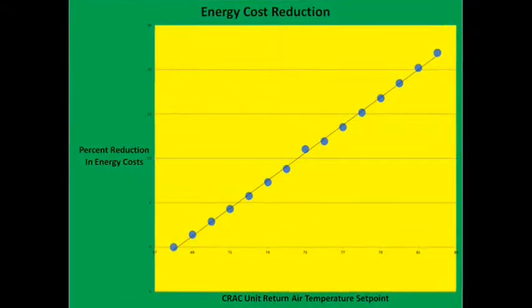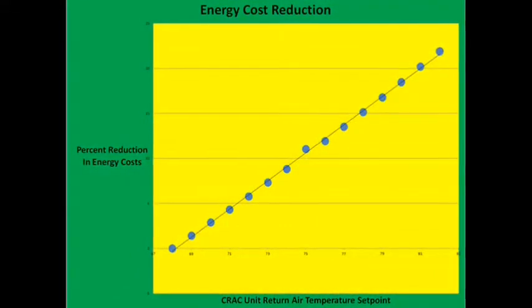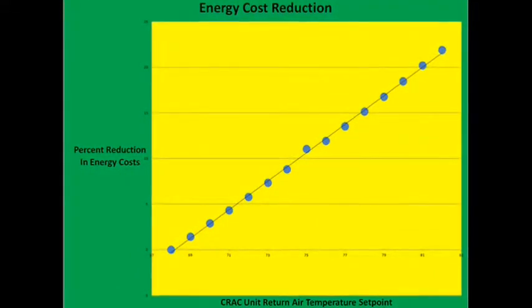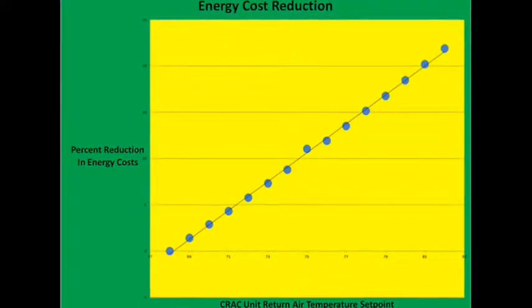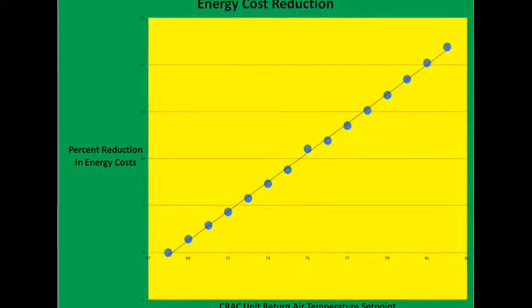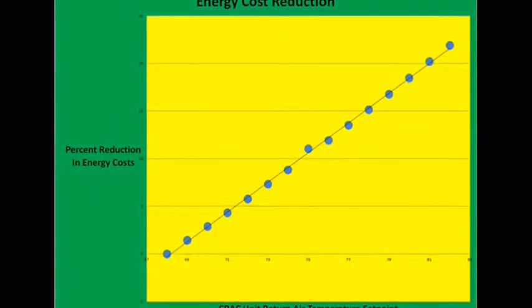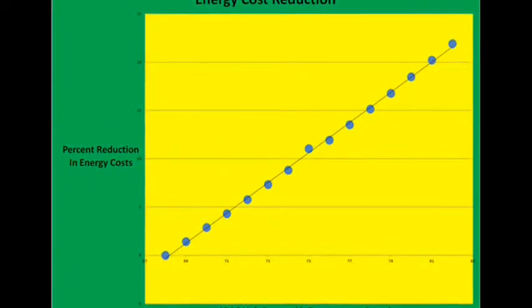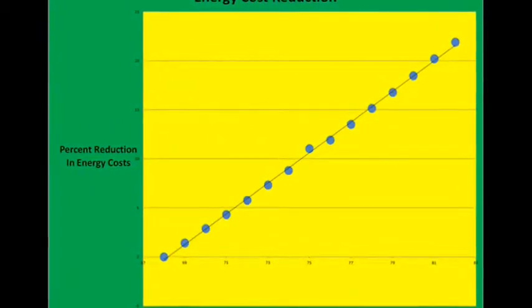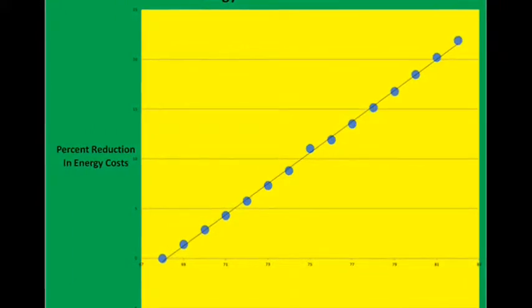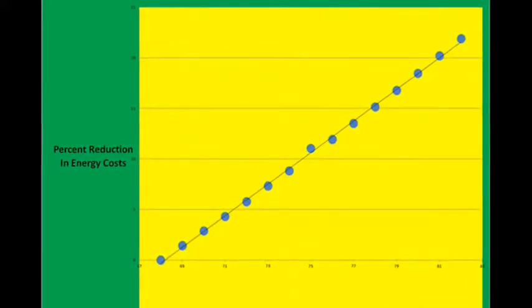This plot was generated from compressor manufacturer data and depicts the energy cost reduction associated with raising CRAC unit return air temperature set points. A 22% cut in compressor running costs may be achieved by stepping up set points from 68 degrees Fahrenheit to 82 degrees Fahrenheit.